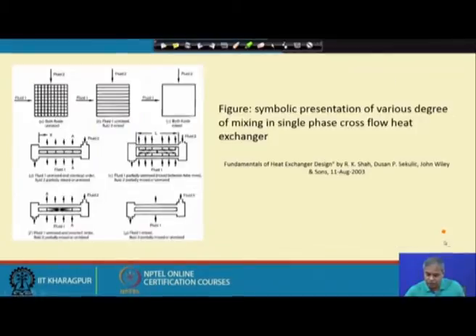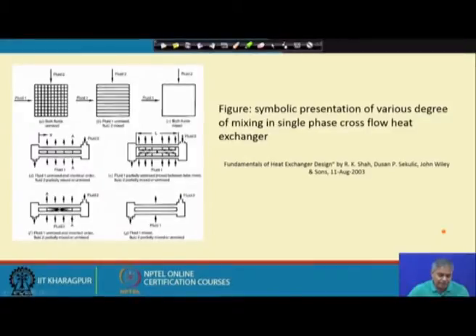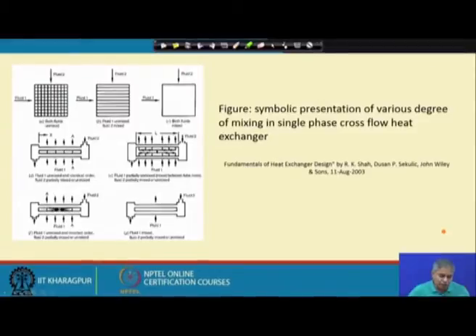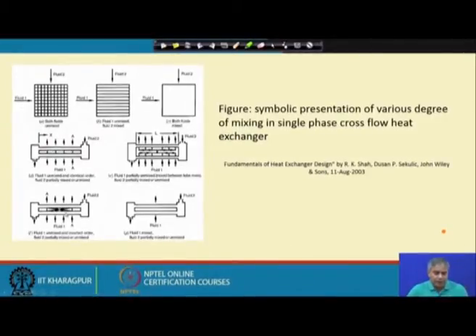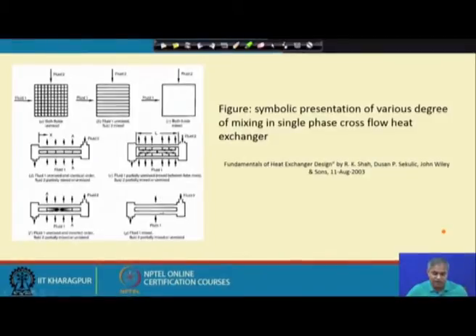Going back: when fluid 1 comes out it is sent to the other side of the heat exchanger, and from this end fluid 1 is sent to the front end. This is how we can reduce the temperature variation at the exit of the heat exchanger. In this arrangement fluid 1 is totally mixed because there is no passage in between, and fluid 2 is partially mixed or unmixed.